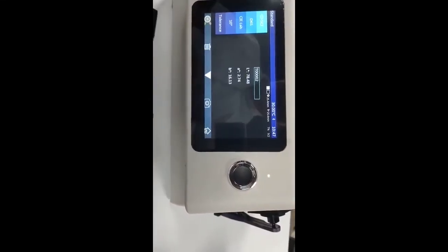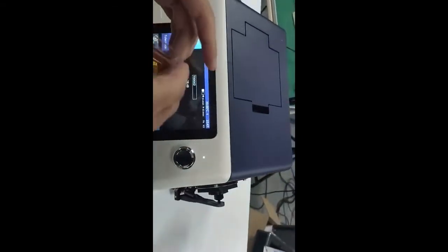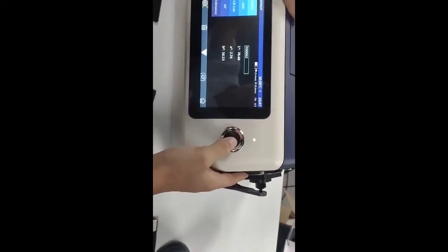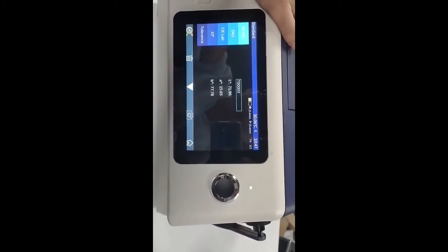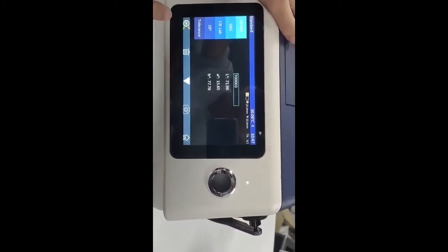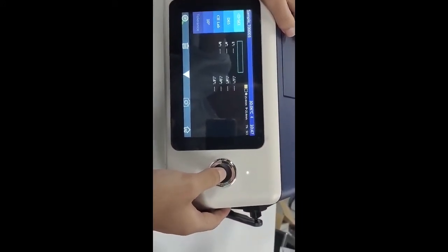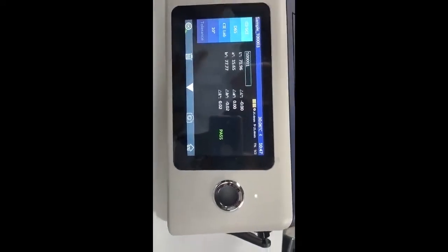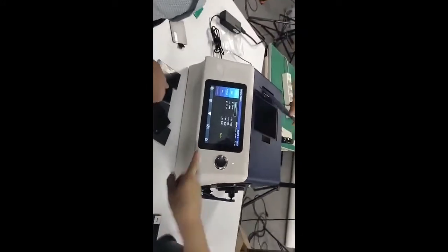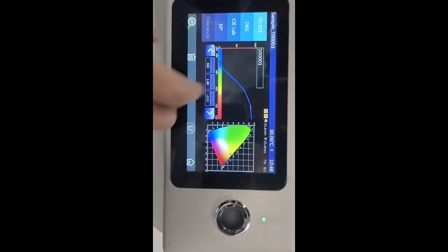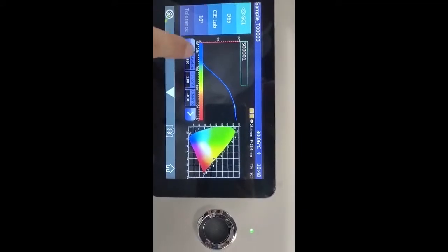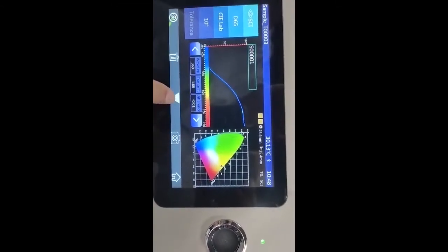And we go to the measurement interface to measure the transparent liquid. Put the sample here. Be careful with the liquid. Don't spill it out. Press the button. Okay. Measurement done. Every measurement you can check the reflectance rate here.